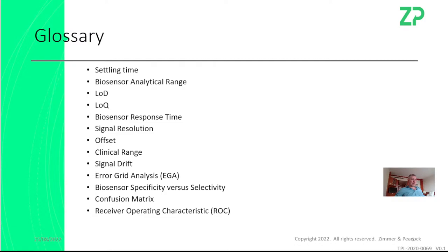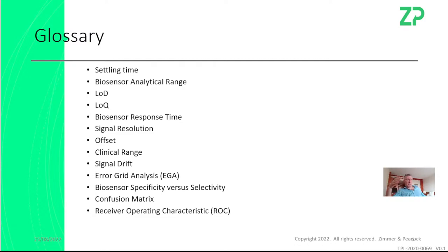Resolution is always a really interesting one because people ask what our resolution is. At the same time, there's an entire system at play — the sensor can often have good resolution, but at a system level there's all sorts of noise, the most obvious being electronic noise. People don't often ask us about offset, but I will discuss that. Clinical range — the one thing people very rarely ask us is, can it work within the clinical range? We often ask people what the clinical range is, and you find out during a project that what people think it is, is not actually the clinical range.